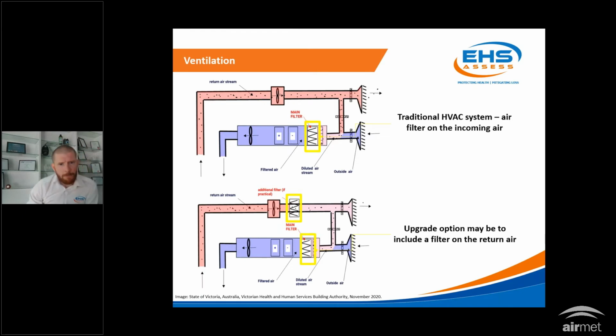The diagram at the bottom is an example of what can occur. You can add extra filters onto those systems, and on the return air in particular - where you're recirculating a component of that air - you can add another filter capable of filtering particles down to very small micron sizes. What you're doing is filtering any return air before it gets recirculated back into the system.